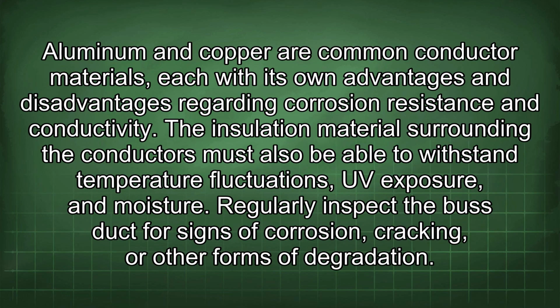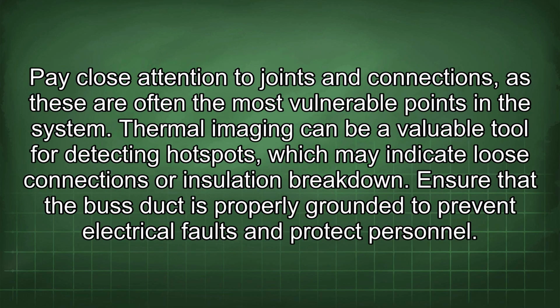Aluminum and copper are common conductor materials, each with its own advantages and disadvantages regarding corrosion resistance and conductivity. The insulation material surrounding the conductors must also be able to withstand temperature fluctuations, UV exposure, and moisture. Regularly inspect the bus duct for signs of corrosion, cracking, or other forms of degradation. Pay close attention to joints and connections, as these are often the most vulnerable points in the system. Thermal imaging can be a valuable tool for detecting hotspots, which may indicate loose connections or insulation breakdown.